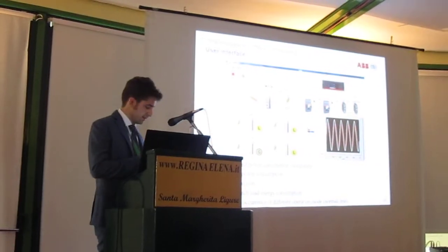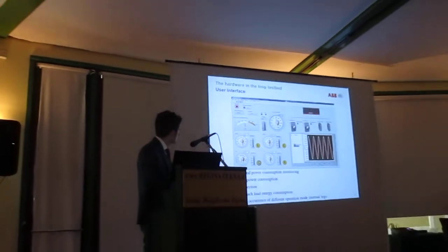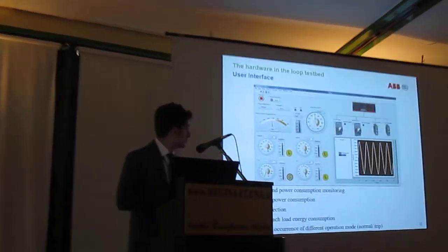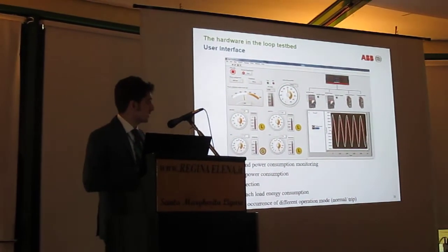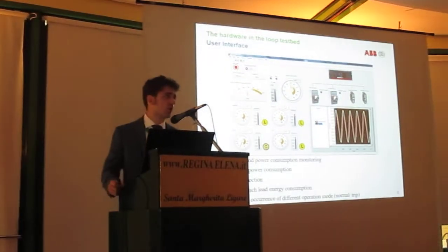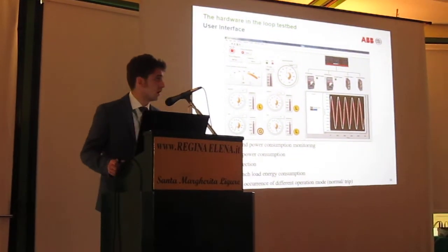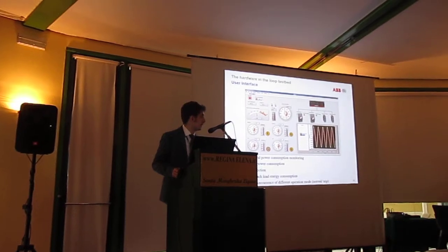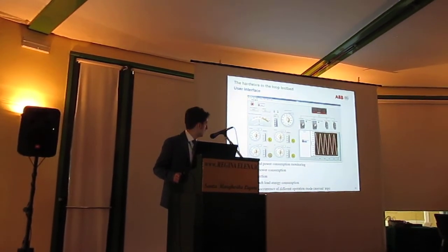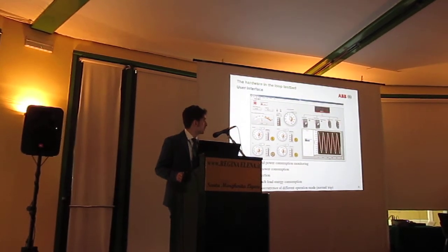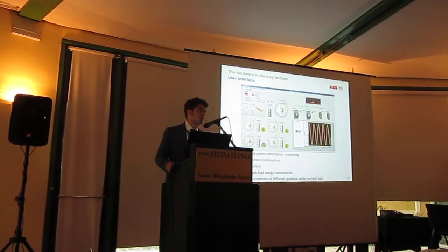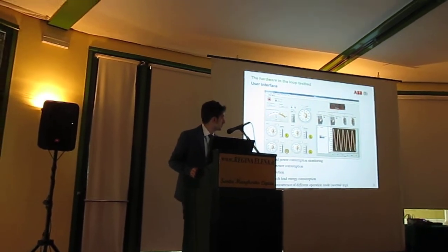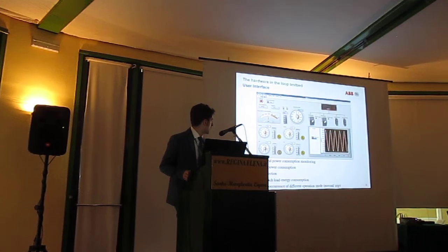If you also have a look at these features, these tools, the user can change the absorbed power from 0 to its nominal value of 1. Also, the power factor can be set from 0 to 1. Also, the behavior of the load from inductive to capacitive, and from load to generator, is adjustable. Also, the graphical status of the loads is presented with trip mode indication, and the corresponding input voltage and currents, to give clients an idea of the displacement factor, the power factor, and what the total absorbed power looks like.